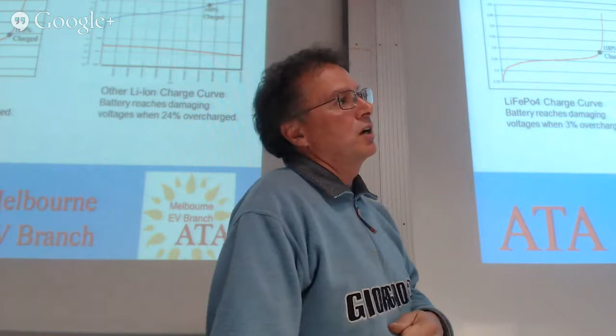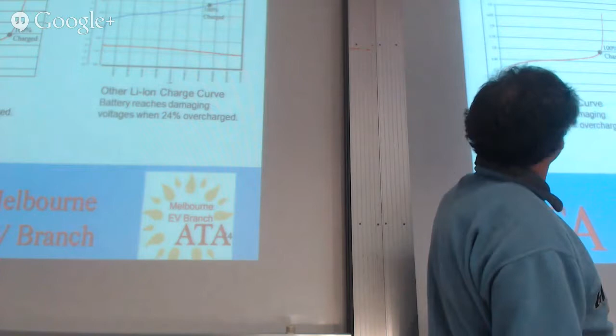Now here we've got two different types of batteries, and I'm comparing the actual charge curves for them. With the LiFePO4 battery, once it's charged, it reaches about 3.55 volts. If you continue to overcharge it, it will very quickly rise above 4 volts, whereby the battery will start to be damaged and age prematurely from overcharging. So at 100% charge, it's at about just on 3.5 volts.